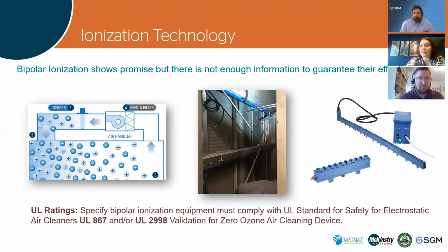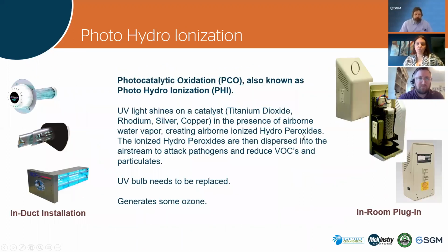And then also when you're looking at this technology, understand the difference between needle point and non-needle point bipolar ionization. But again, your options to fall within the guidelines of the UL standards are pretty limited in the marketplace. So another type of ionization is photocatalytic oxidation, PCO, also known as photohydroionization, PHI. You can see in-duct installation examples on the left, and on the right you can see some residential examples. Someone brought up a question about what we can do in our residences, and this is an example that could be added to residences.